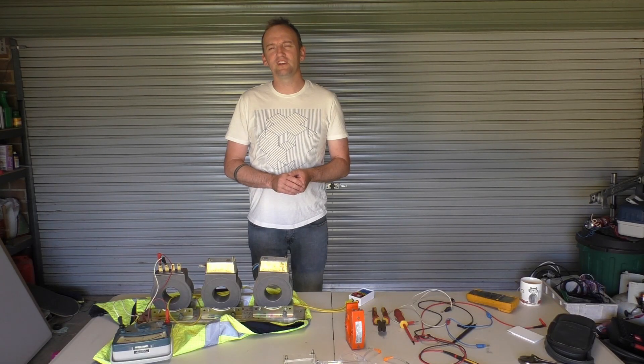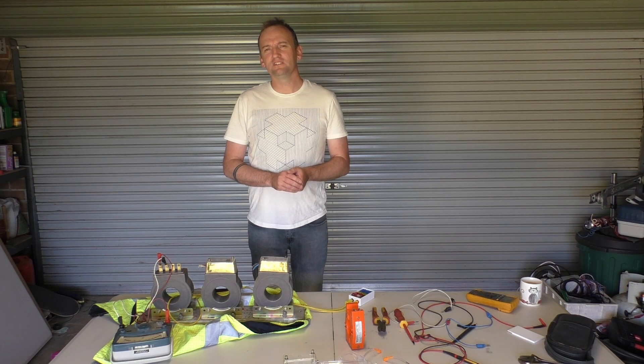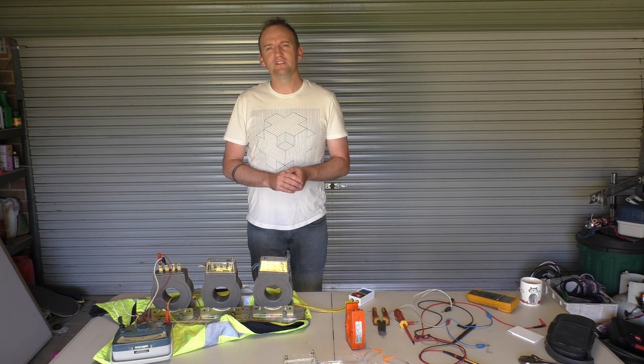This is a quick demonstration of how you do a flick test on a current transformer to work out its polarity using an analogue meter and a DC battery.